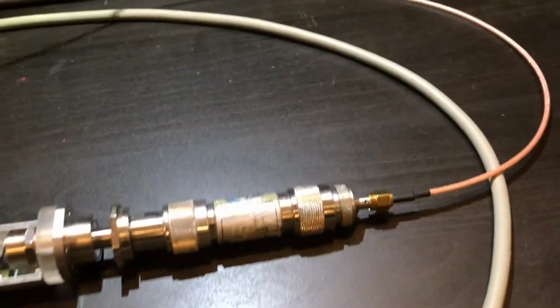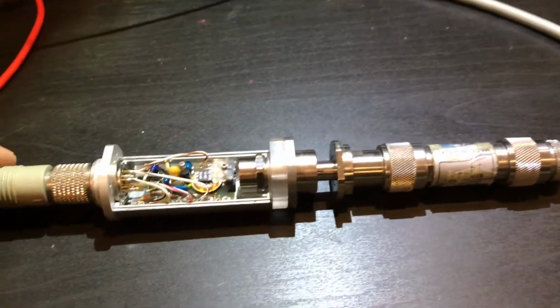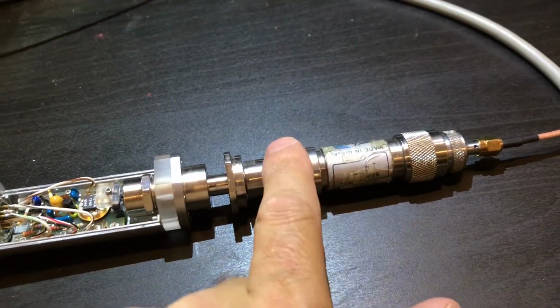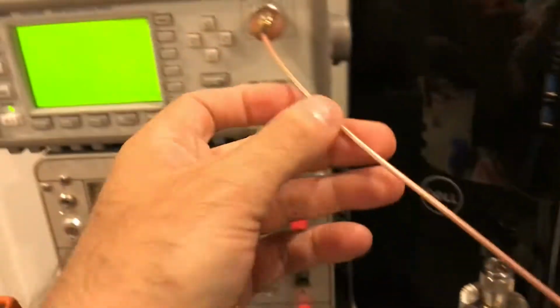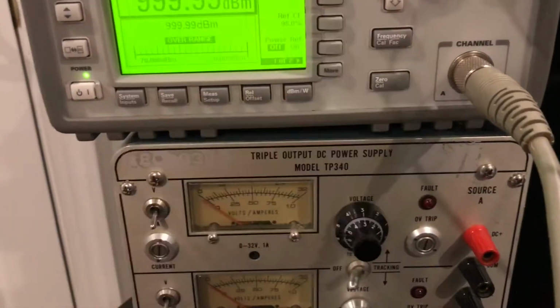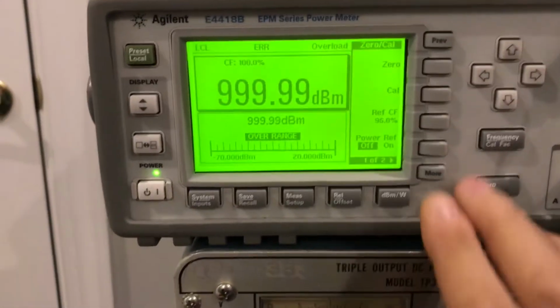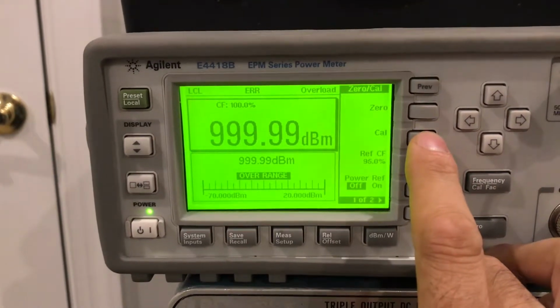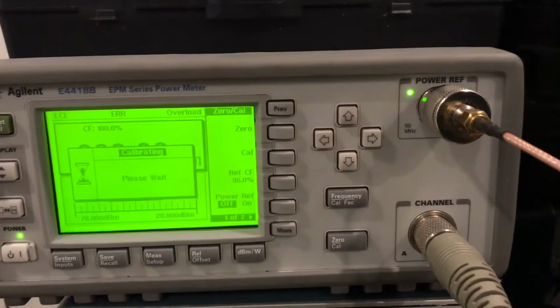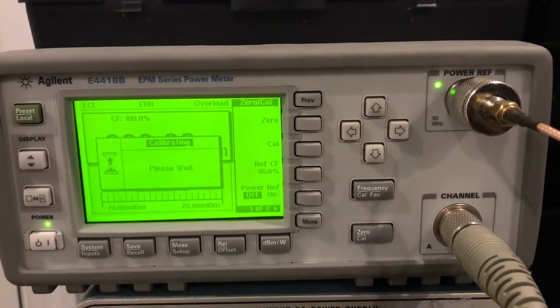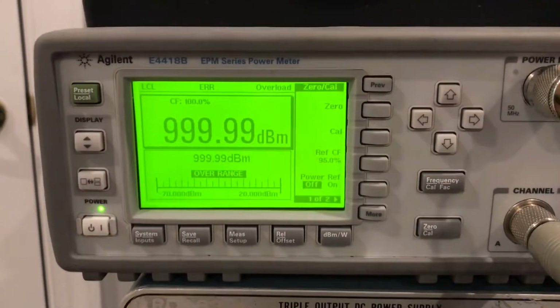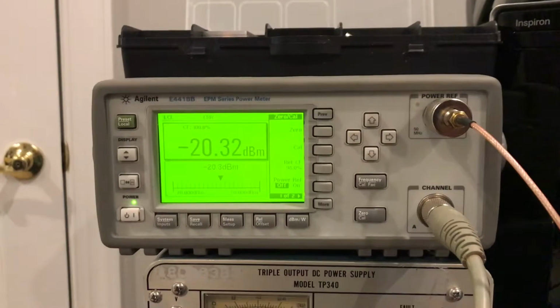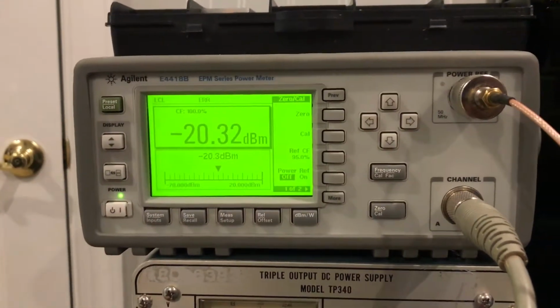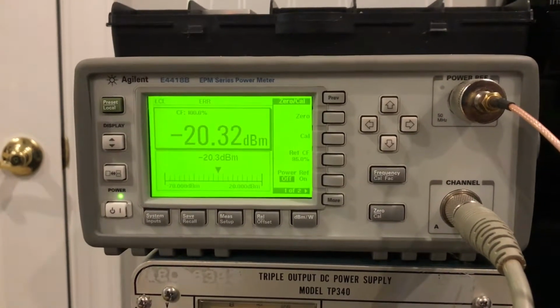So what we'll do now is I've hooked this up just to make things easier. I know this is not the ideal setup, but it'll work for testing. I've put the reference attenuator in line with the sensor, and I've got that fed back through this coax to the reference power port on the power meter. Now we'll run the cal, and we'll cal the unit to minus 20 dBm. So we've got the LED lit there, putting the reference calibration signal on the sensor, and there's our cal error. So we've seen that we can't zero it, and we can't seem to calibrate the sensor either.